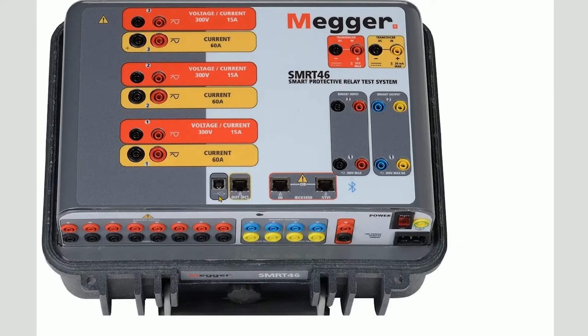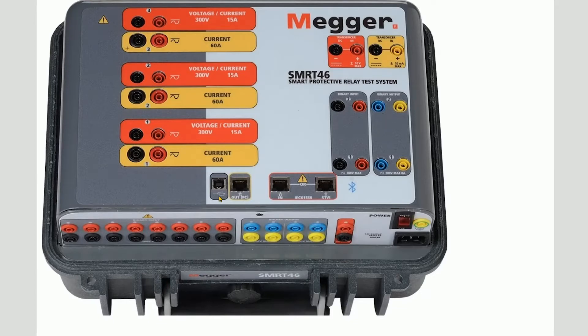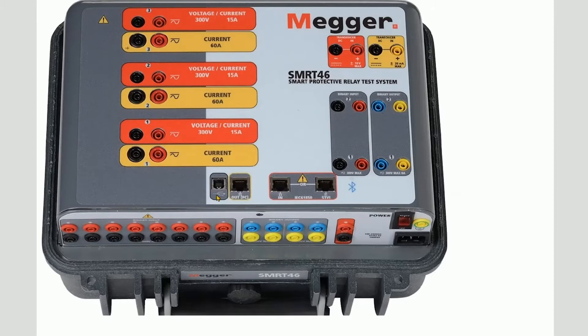Serial over USB. Note that this is a USB Type-B port. There is an RS-232 chip embedded in the test set. When you plug a USB cable into this port, it will set up a new COM port on your computer. Use Device Manager to discover the COM port number and begin communication.